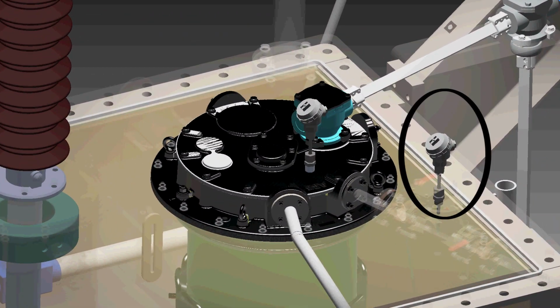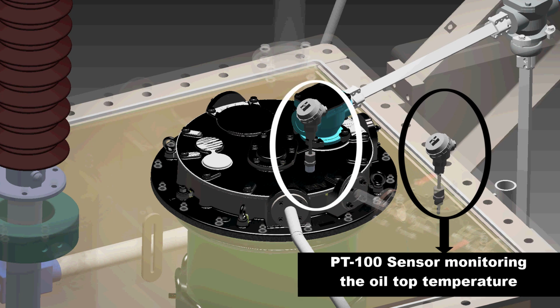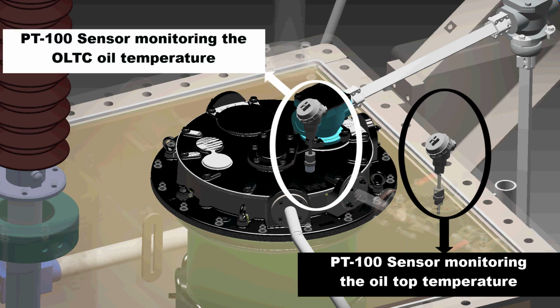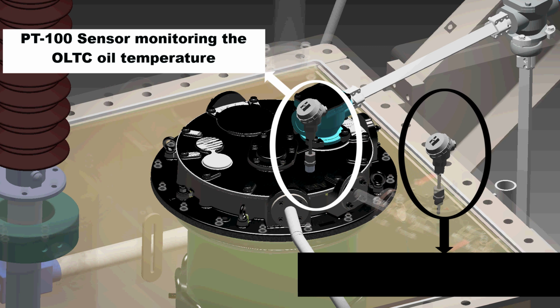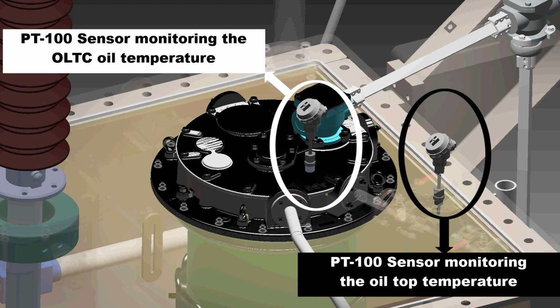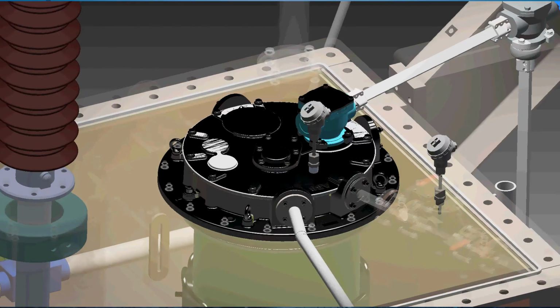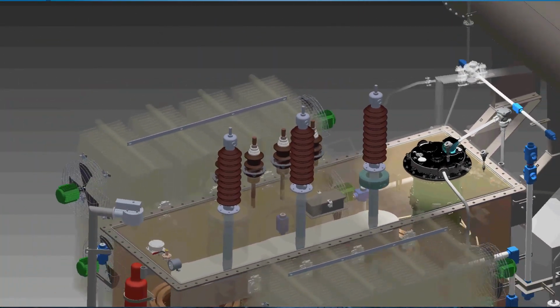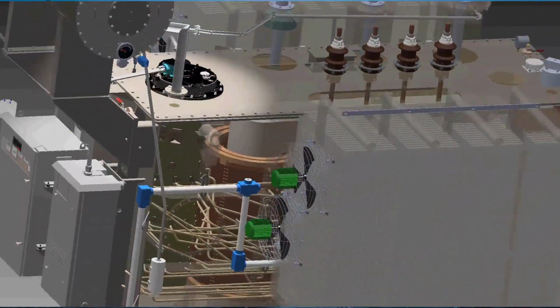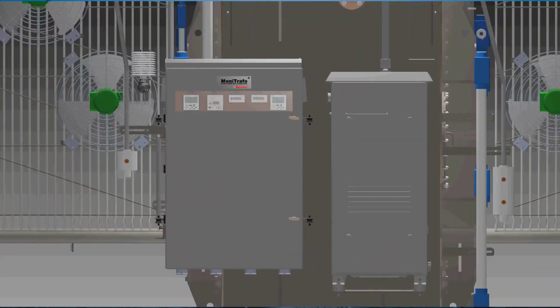It is quite simple to apply. Just use a PT100 in the transformer oil tank and the second type PT100 sensor in the tap changer oil tank. Therefore, the temperature differential between transformer oil and the tap changer oil will be monitored continuously. And if there is a significant temperature difference, the indication of a failure or defect that, if corrected at its beginning, may prevent an interruption or a shutdown of the transformer, increasing the transformer availability.